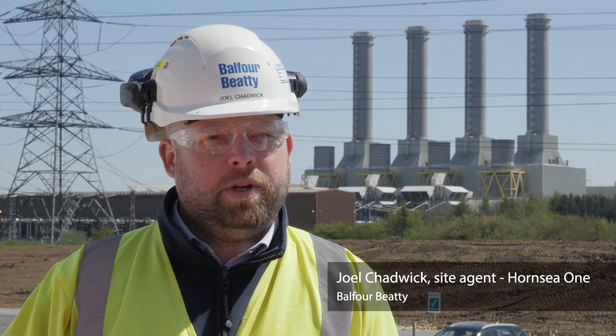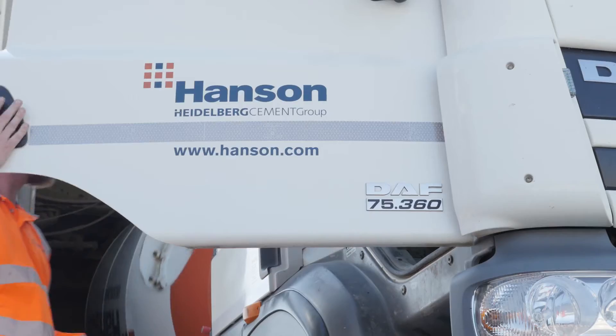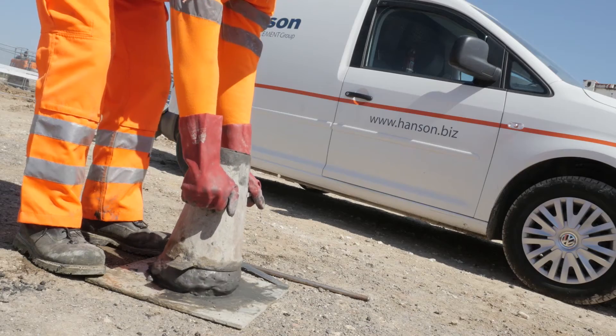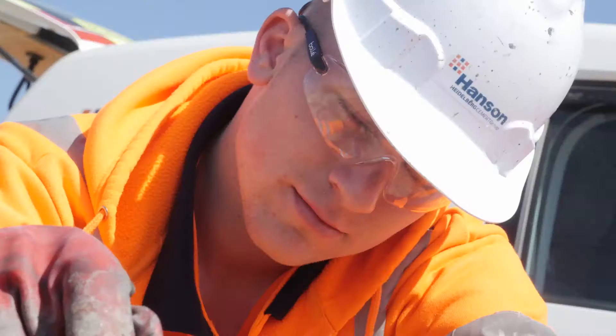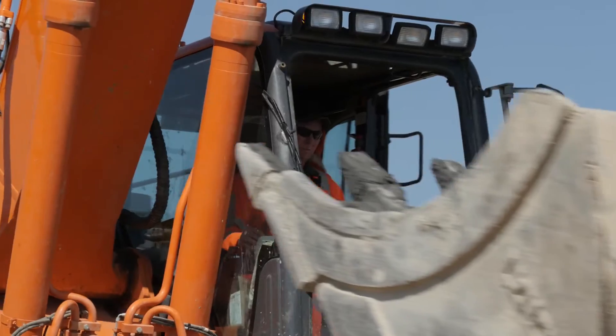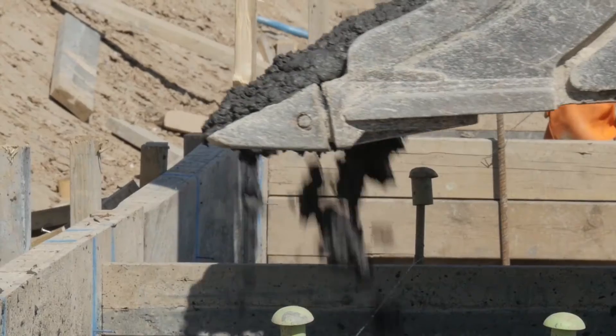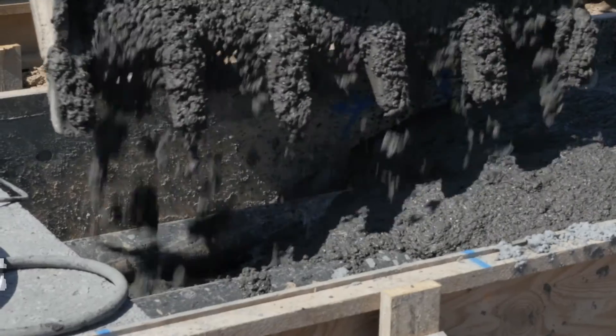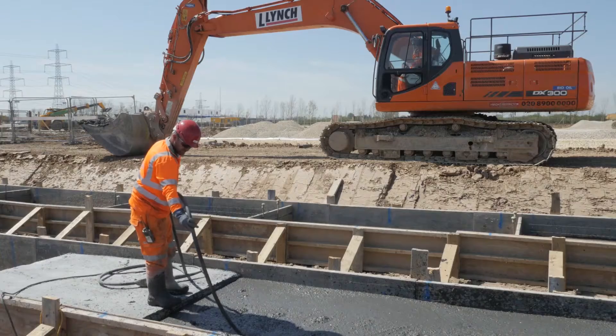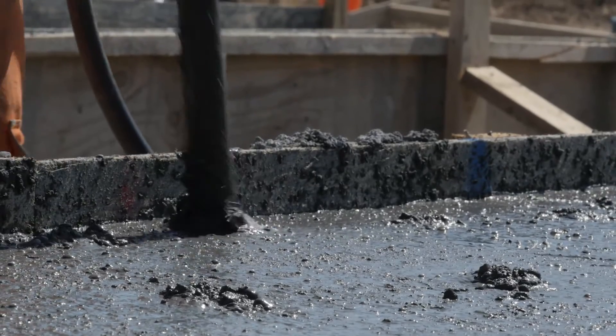My name's Joel Chadwick. I'm a site agent for Balfour Beatty on Hornsea 1. We've used Hanson as a supplier for a number of years. The PowerCrete is a unique product and they've been able to offer us a lot of support. It's an innovative product — it allows us to work it as normal concrete, making it much easier to place. PowerCrete was specified by the client because of its high thermal conductivity. It allows the cables to remain cooler, increases the capacity, and ultimately gives a better supply to National Grid.